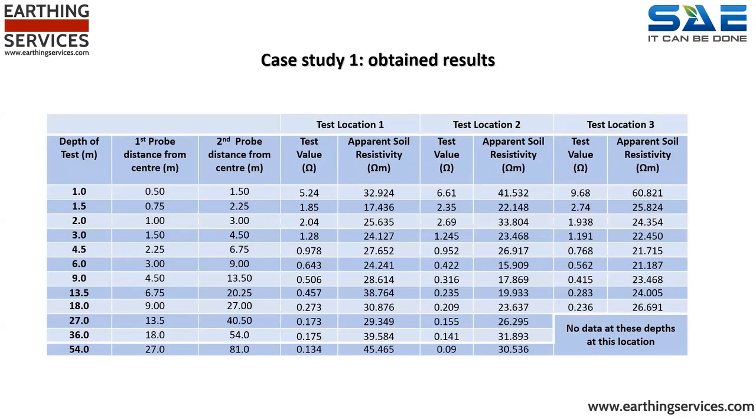So let's run a case study and see whether obtaining soil resistivity data would be useful or not. This table of data was obtained from a test location in the southeast of the UK. This testing was undertaken to provide an evaluative model as part of product testing, where the commissioning party was comparing the performance of a number of electrode types and configurations. For their evaluation, 5 conductor variants were installed, and this was done prior to processing the data set obtained from soil resistivity testing.